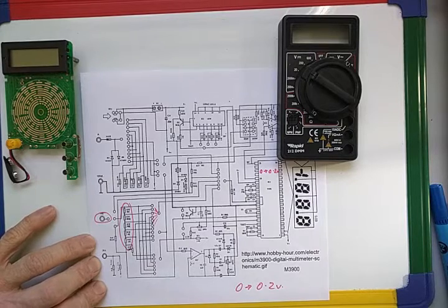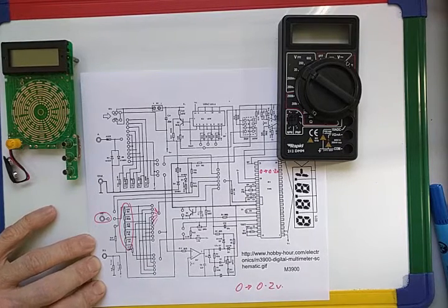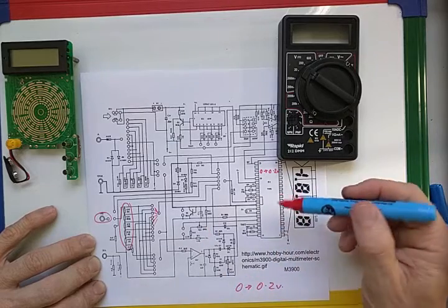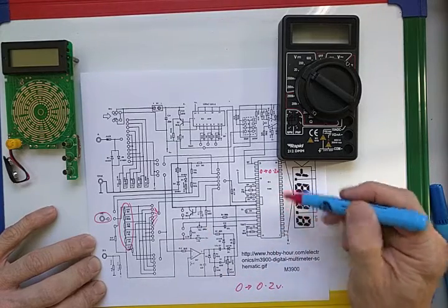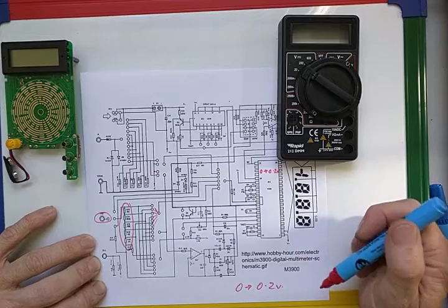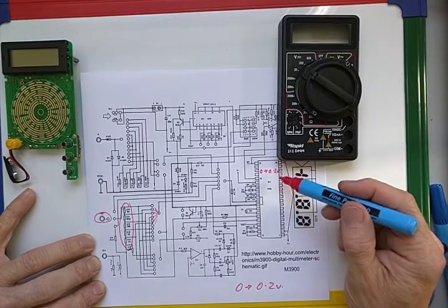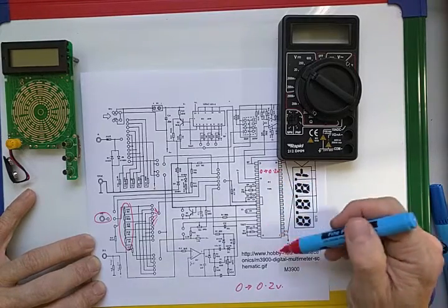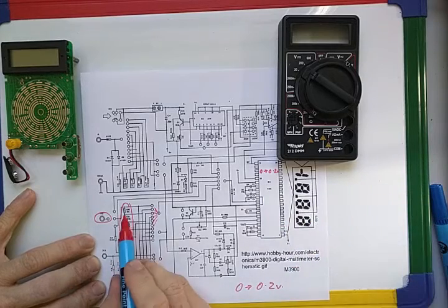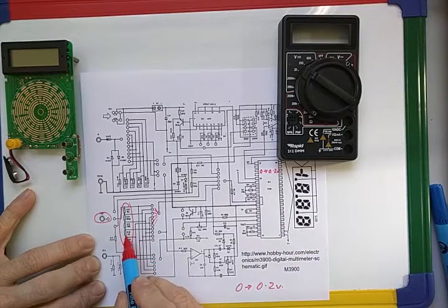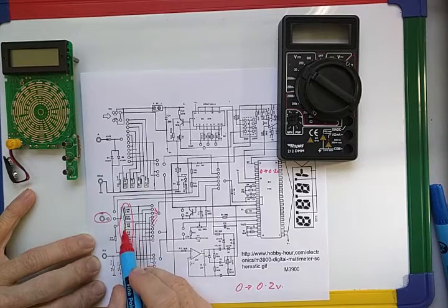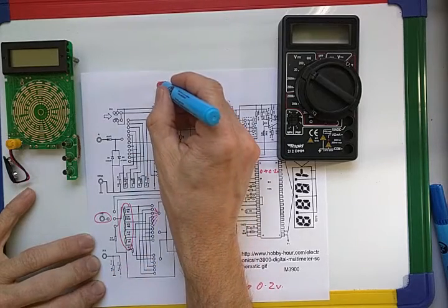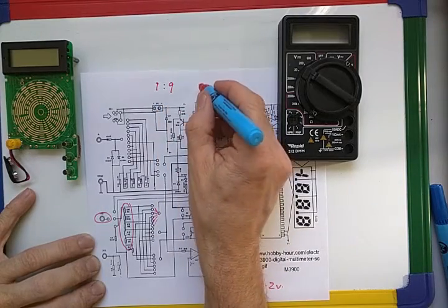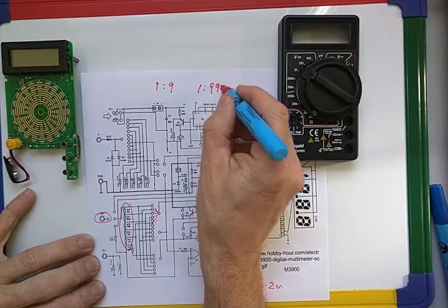So if you're measuring 15 volts, you'll actually find there's only 150 millivolts going to the main processor. If you're measuring 190 volts, you'll find there's 0.19 volts going to the main processor. That's what these dropping resistors are here - series resistors that drop down in a ratio of 1 to 9, 1 to 99, or maybe even 1 to 999.